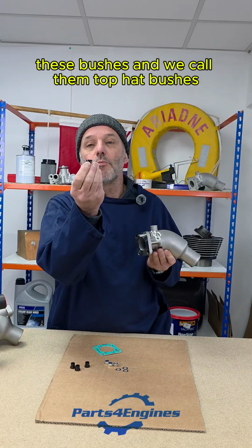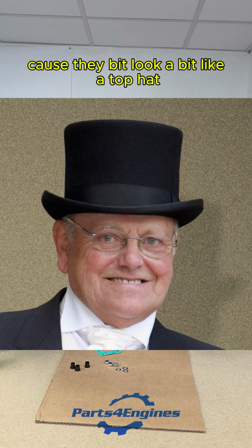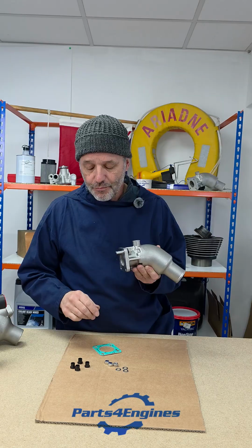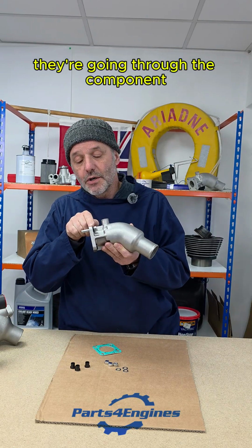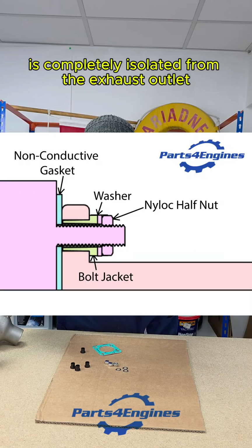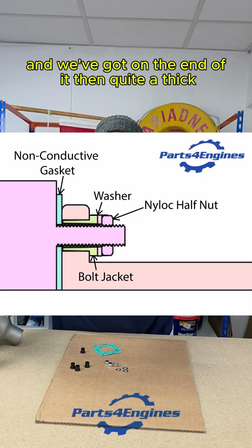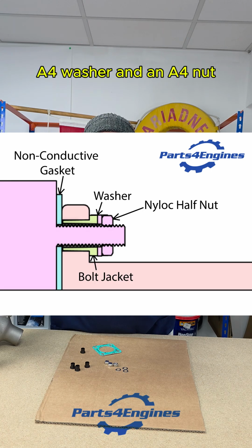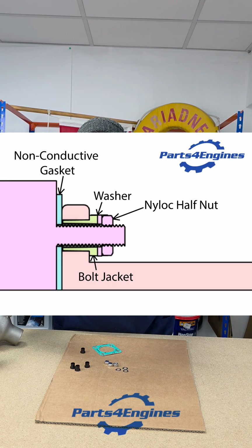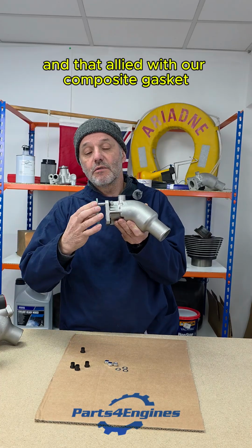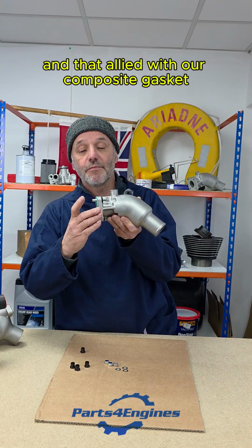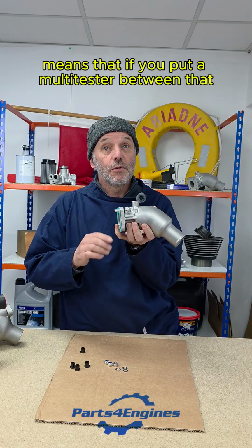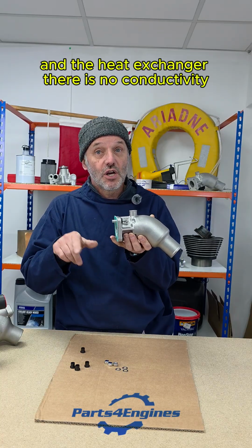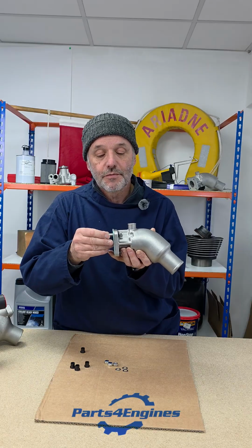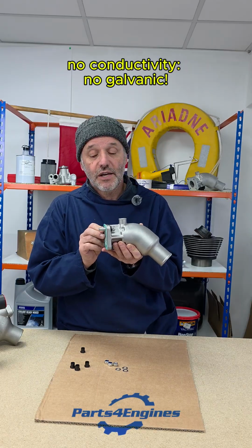These bushes - we call them top hat bushes because they look a bit like a top hat, the old traditional top hat - go through the component, and therefore the stud that comes through is completely isolated from the exhaust outlet. We've got on the end of it then quite a thick A4 washer and an A4 nut. And that, allied with our composite gasket, means that if you put a multi-tester between that and the heat exchanger, there is no conductivity. No conductivity, no galvanic corrosion.